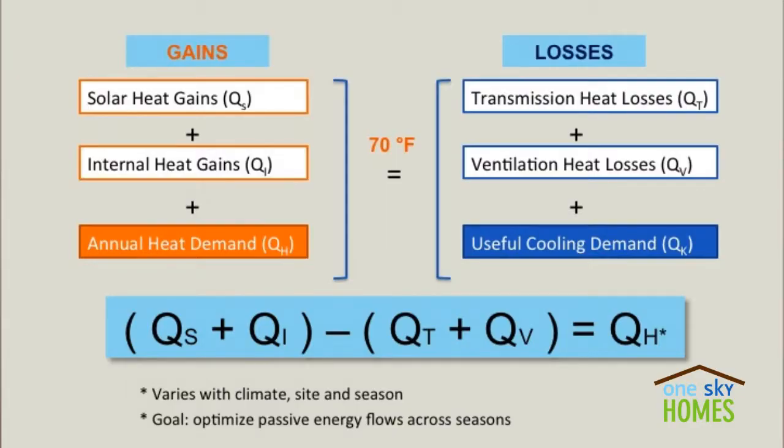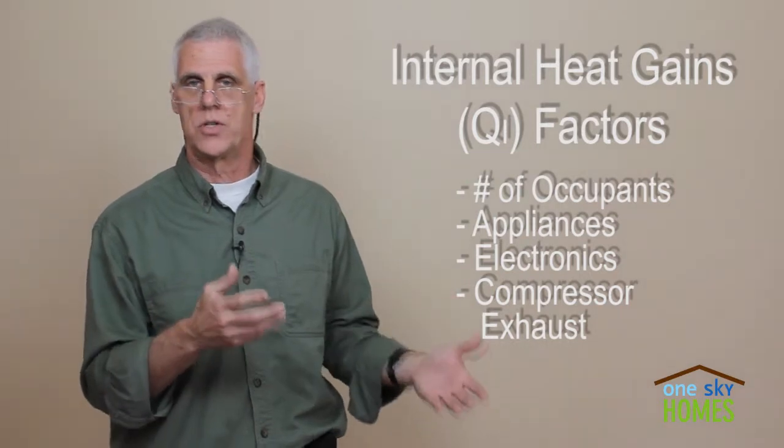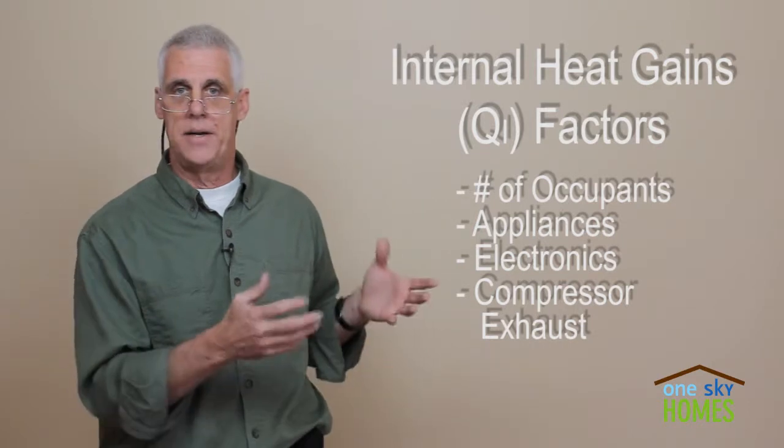The other side of the gain variable is QI — internal heat gains. We have to understand how many occupants we have in the building, whether it's a school, office building, or home, because we all generate a certain amount of heat. And then, of course, there are the appliances and electronics. Essentially anything that uses electricity creates heat. There's refrigeration equipment where there's exhaust heat off of compressors. All of these are internal heat gains and they add to the passive gains in the building.